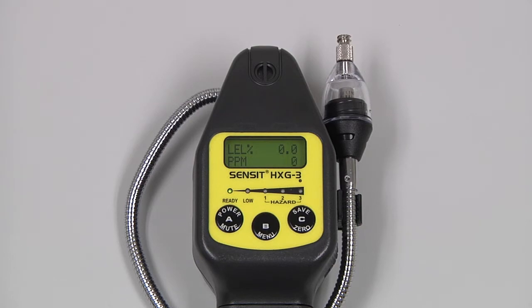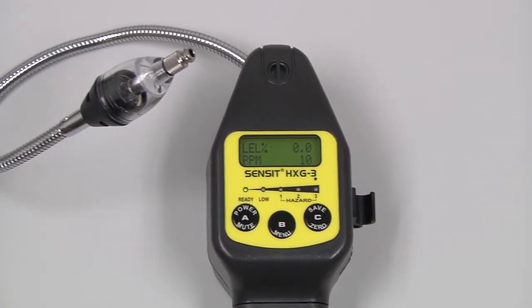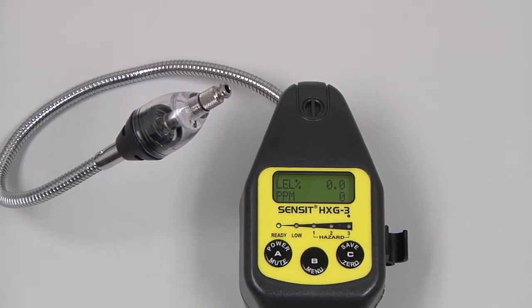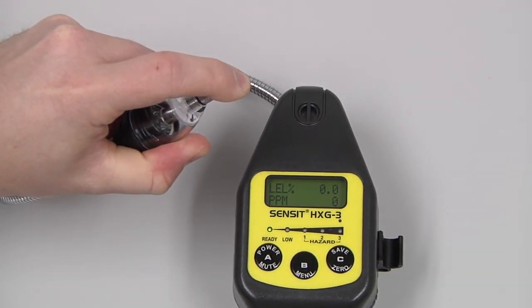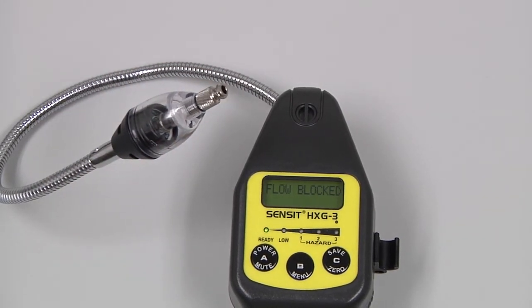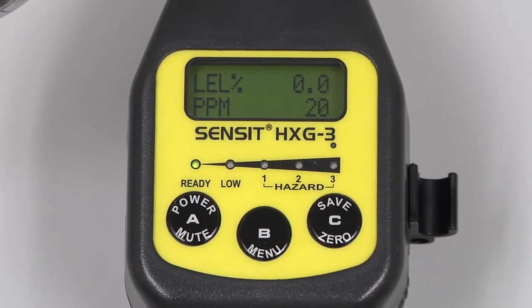Before use, we need to check the integrity of the sensor cap assembly. If the filter is torn or excessively dirty, the sensor cap will need to be replaced. We also need to do a flow block check. You can do that by blocking the inlet with a finger, and within a couple of seconds the instrument should indicate flow blocked. We will then be ready for use.